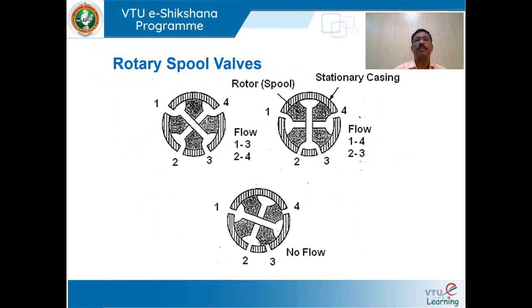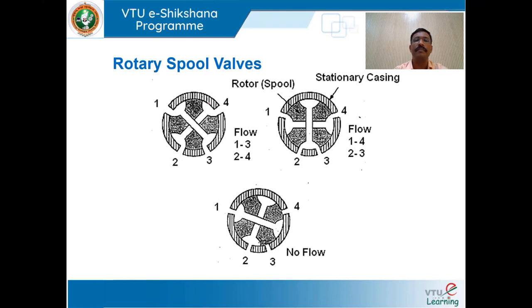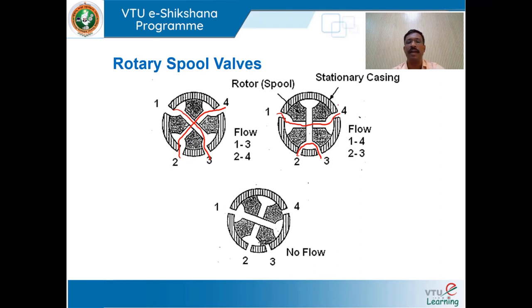We shall discuss the rotary spool valve, as opposed to the sliding spool valve discussed so far. In the rotary spool valve, the spool rotates within the valve body. In one position, port 2 is open to 4 and port 1 is open to 3. When the spool rotates, port 2 is open to 3 and port 1 is open to 4. Rotating again results in no flow across the ports.